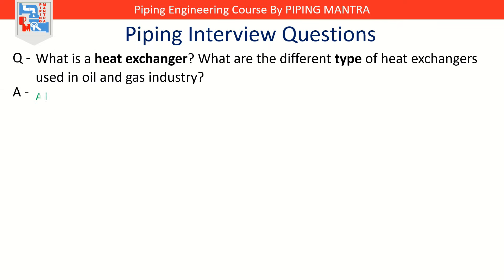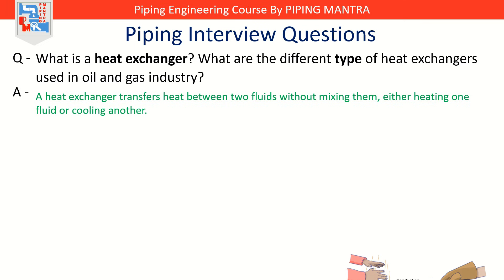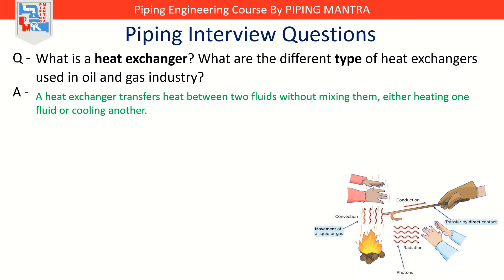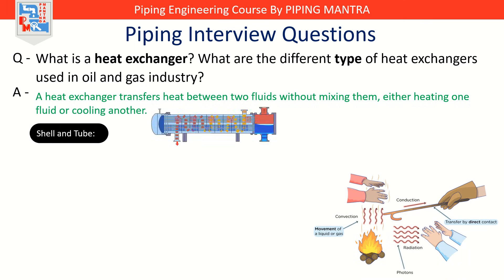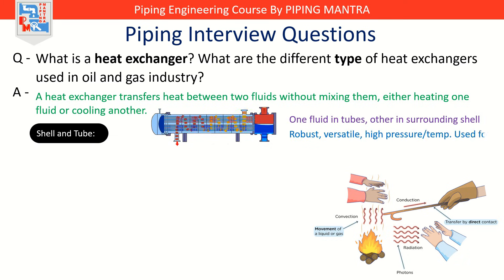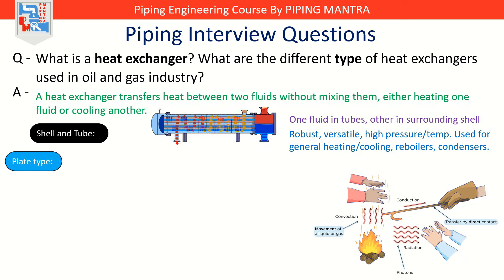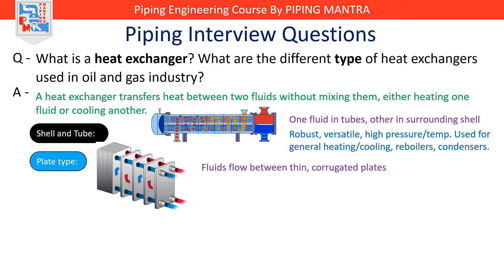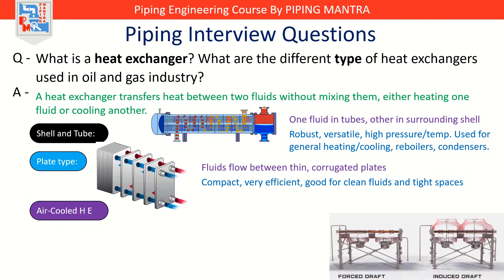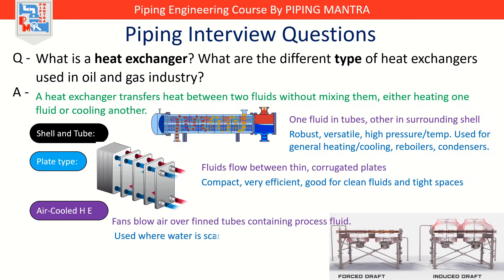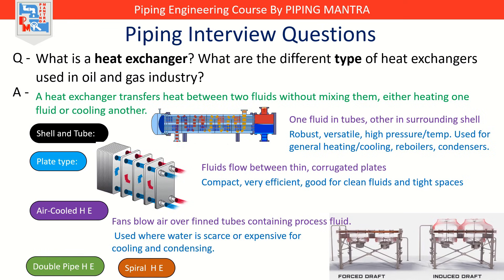What is a heat exchanger and what are the different types? A heat exchanger is simply a device that transfers heat between two fluids without mixing them. Types you will see in oil and gas are: Shell and Tube — one fluid inside tubes, the other around them in a shell, very robust and great for high pressure or temperature. Plate type — fluids pass between thin corrugated plates, compact, very efficient, and perfect for tight spaces. Air cooler — fans blow air over finned tubes, great when water is scarce. Double pipe and spiral — used for special applications, smaller duties, or viscous fluids.